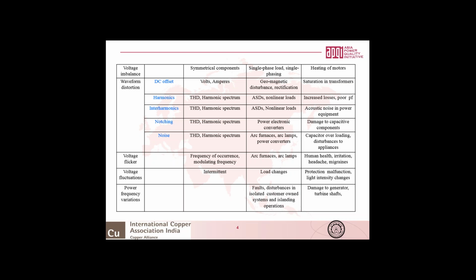Harmonics cause increased losses and poor power factor in the distribution system. Interharmonics cause acoustic noise in power equipment. Notching causes damage to the capacitive component, and noise causes capacitor over voltage and disturbances to appliances. Another power quality problem is voltage flicker, which causes human health effects: irritation, headache, and migraines. And voltage fluctuations, of course, cause protection to malfunction and light intensity changes, and power frequency variations cause damage to generator, turbine, shaft, and many other such problems in the system.